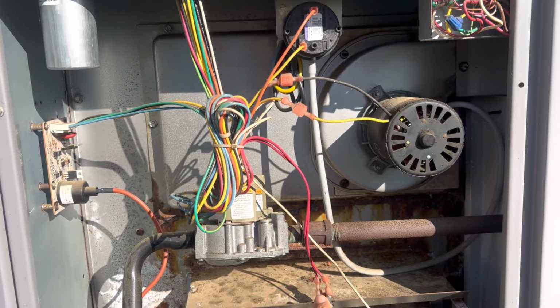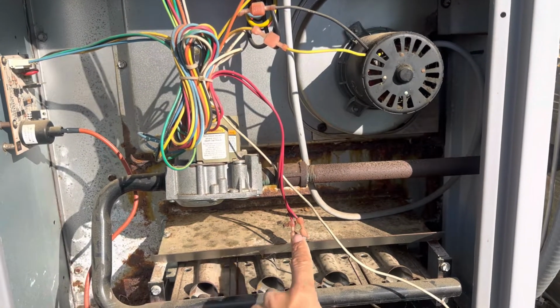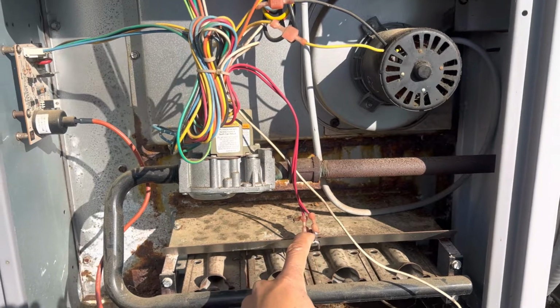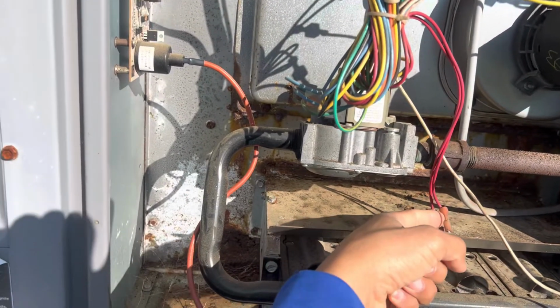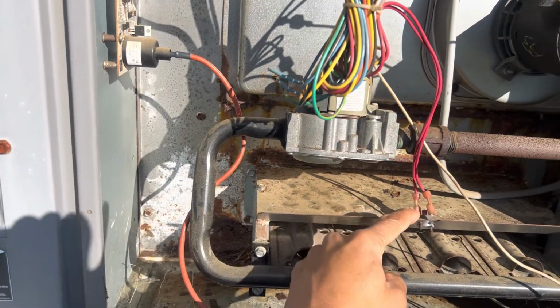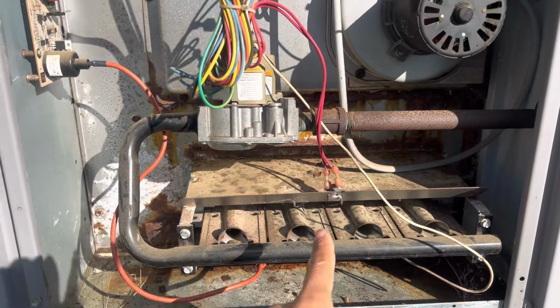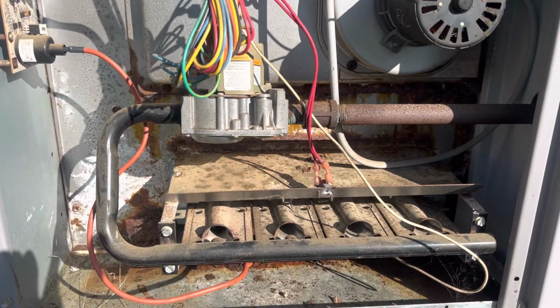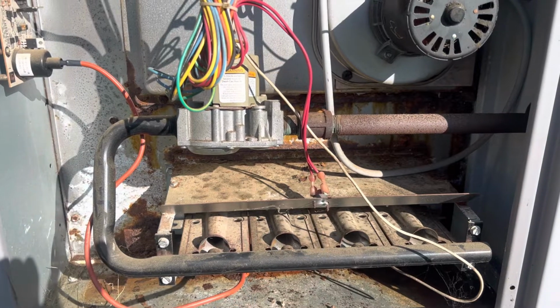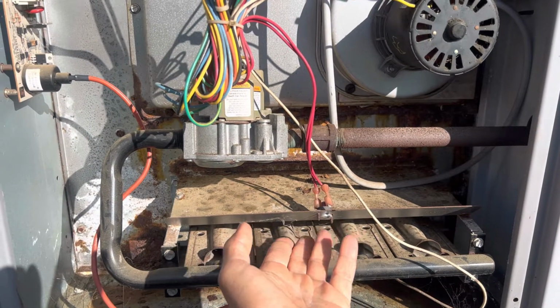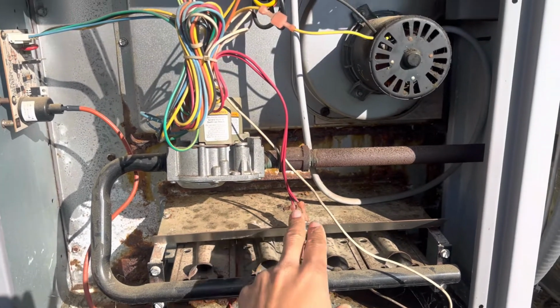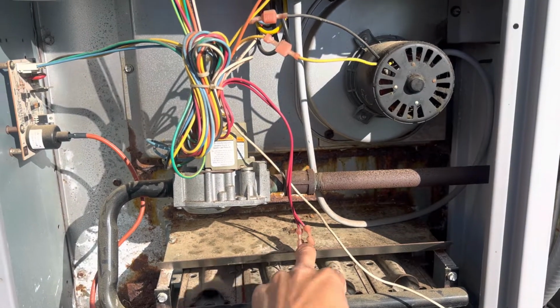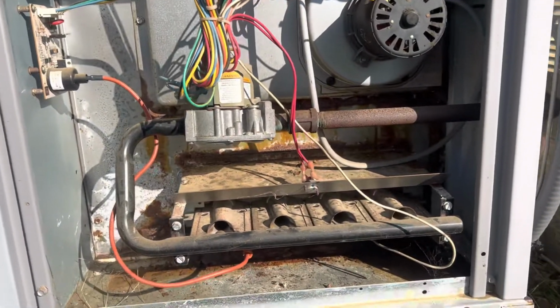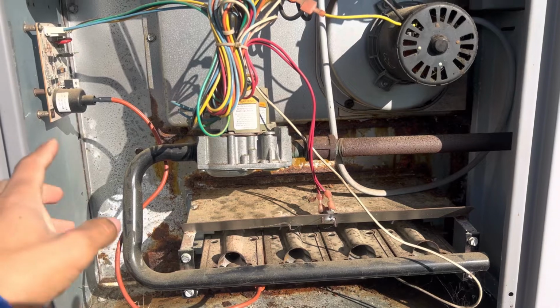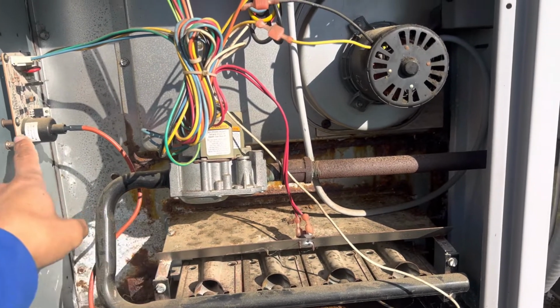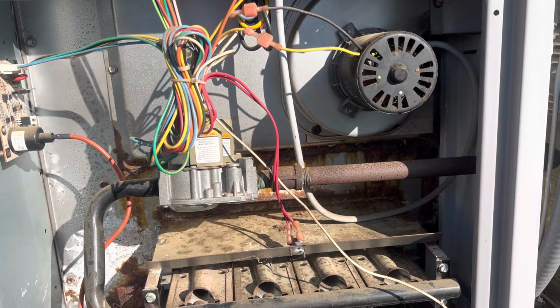Then the system is going to check rollout switch. It's going to make sure this rollout switch is closed. One quick tip, there's a little resettable button on a lot of rollout switches. If a rollout switch is tripped, that's not the problem with the furnace. If a rollout switch trips, that's a sign of another problem, okay? So the safeties are closed, rollout switch, pressure switch, high limit switch.